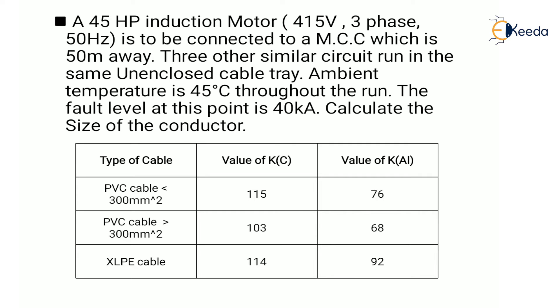Here we have a table showing the type of cable and the value of K, which is the constant associated with the type of conductor — for copper and aluminum. For PVC cable less than 300 mm², K for copper is 115 and for aluminum is 76. For PVC cable greater than 300 mm², K for copper is 103 and for aluminum is 68. For XLPE cable, K for copper is 114 and for aluminum is 92.